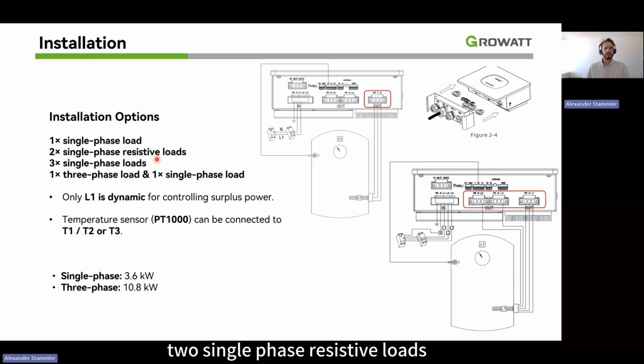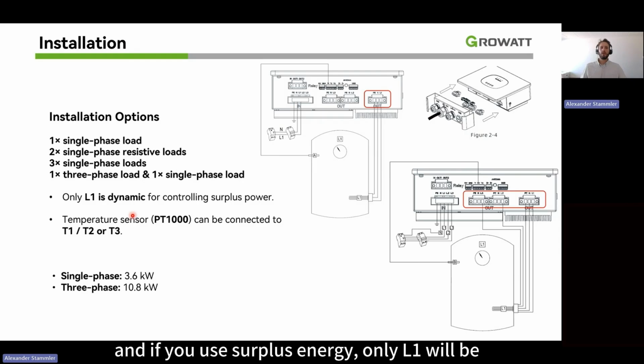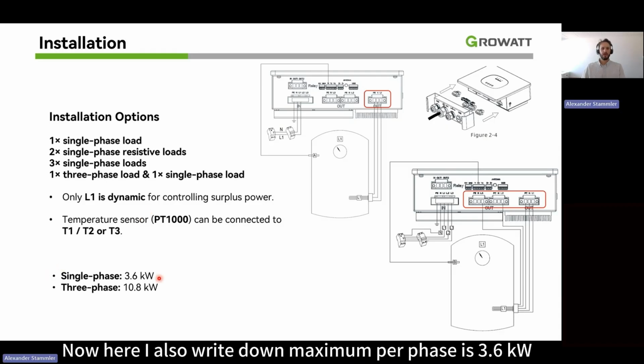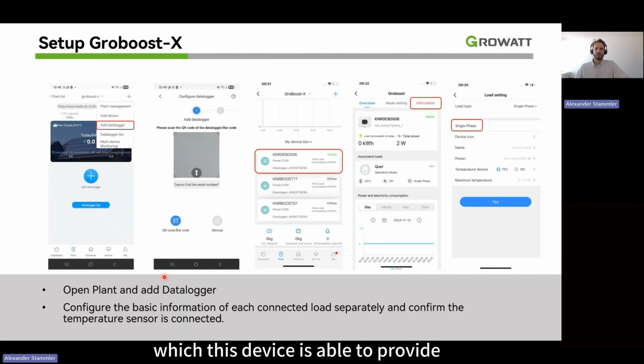Here I also write down that you have the option to use one single-phase load, two single-phase resistive loads, three single-phase loads, or one three-phase load. One three-phase load and one single-phase load is also possible. If you have a three-phase load, only L1 is dynamically controlled, meaning L2 and L3 will provide the same energy throughout, and only L1, if you use surplus energy, will dynamically go up and down according to the energy that is actually provided by your PV. The maximum per phase that this device is able to provide is 3.6 kilowatts.